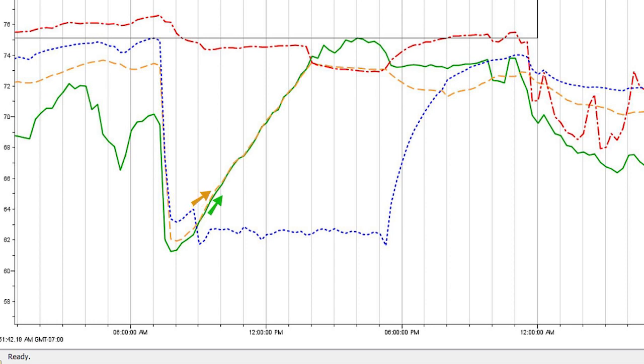We're letting in that cool outside air, and the orange dashed line shows the mixed air temperature, which is tracking very closely with the outside air temperature all the way until we get to about 2 o'clock, where we see that the outside air temperature continues to rise, but the mixed air temperature starts tracking very closely with the return air, which is this red dashed line. So that's indicating that we're no longer economizing, and this is very consistent with what we saw on the BAS trend log. So we can assume that our sensors are calibrated properly.